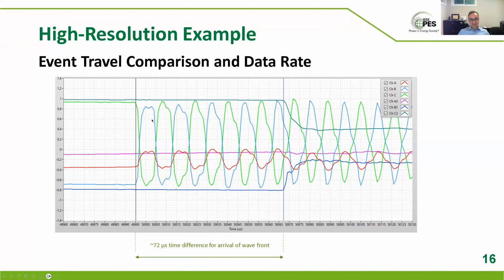What's interesting here is, see this green, this particular terminal of the line is a normally open terminal. So when a fault happens, the traveling wave comes, hits the open terminal, reflects, in a way doubles and reflects, hits the short circuit again, reverses and comes back and reflects, hits the short circuit, reverses again. So every time it hits the short circuit, it reverses polarity. Every time it hits the open end of the line, it just reflects, it doubles and reflects. So you see a reflection pattern.